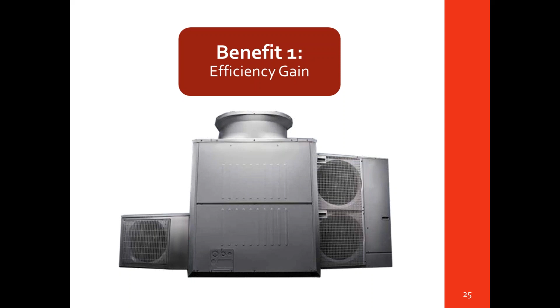With lower cost, one of the ways we can achieve that is through operational awareness, so you can modify heating and cooling strategies. We can use light sensors to measure the actual available light and dim lights, saving energy, or use blinds to reduce solar load. There are optimal start and optimal stop strategies that help reduce use during peak times and can also allow a building to coast at the end of the day to a stop rather than running the full schedule, saving money.